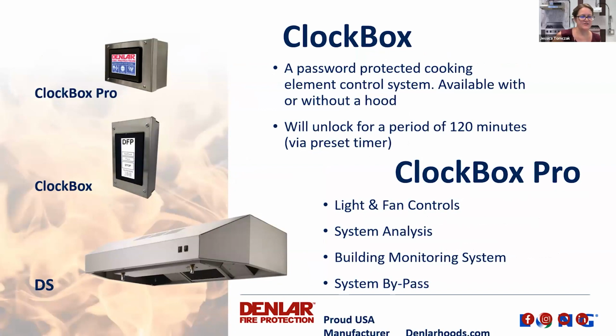The clock box, to answer your question, is a password protected cooking element control system. It can work with or without a hood. The user enters a password, and it unlocks power to the stove for a period of 120 minutes. The reason it's preset to 120 minutes is because that's what's required to be compliant with the NFPA 101 code that I talked about before. In addition, the ClockBox Pro also contains light and fan controls, the ability to provide system analysis and building monitoring, and a system bypass to help with troubleshooting in the field. So it has some additional features beyond just the timer control system that the standard clock box offers.